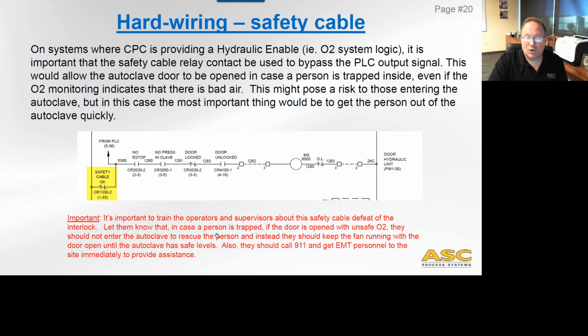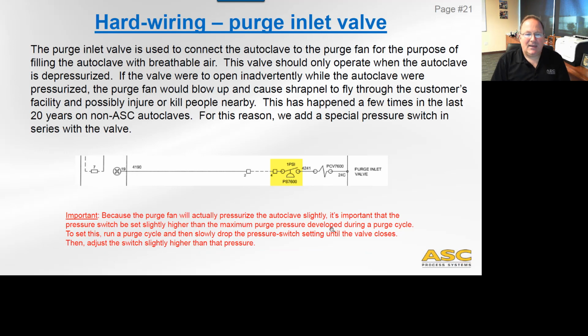What we do want to urge is that when that door opens, keep the fan running and very quickly the oxygen in the autoclave will rise to 19.5%. And so it's just a much quicker way of purging the autoclave in this specific, very serious condition. So, okay, and lastly, purge inlet valve. The purge inlet valve is used to connect the autoclave to the purge fan for the purpose of filling the autoclave with breathable air.